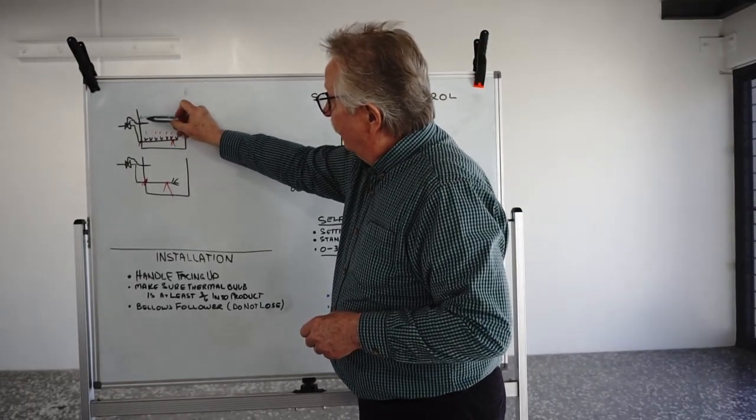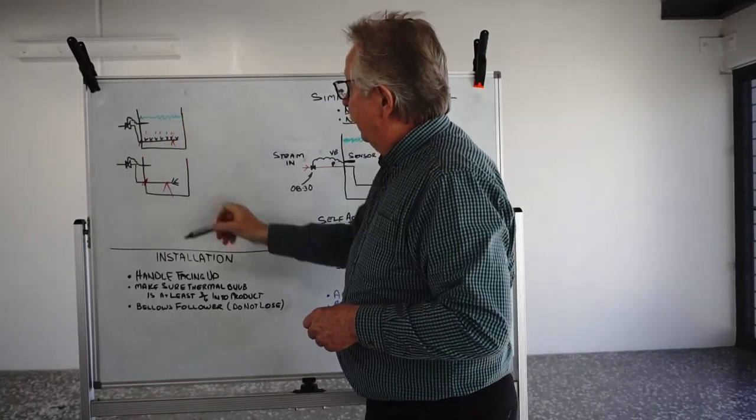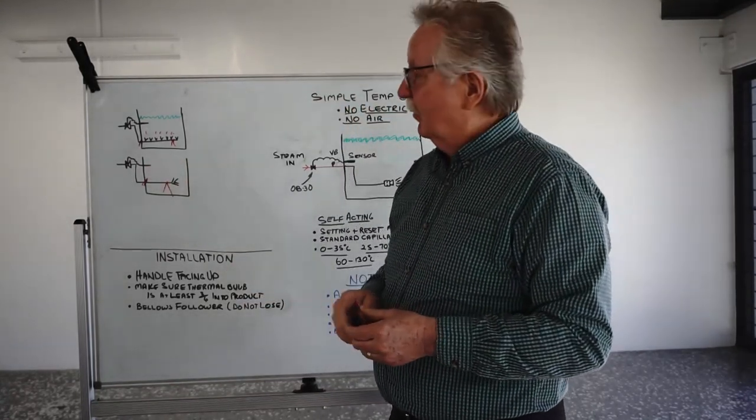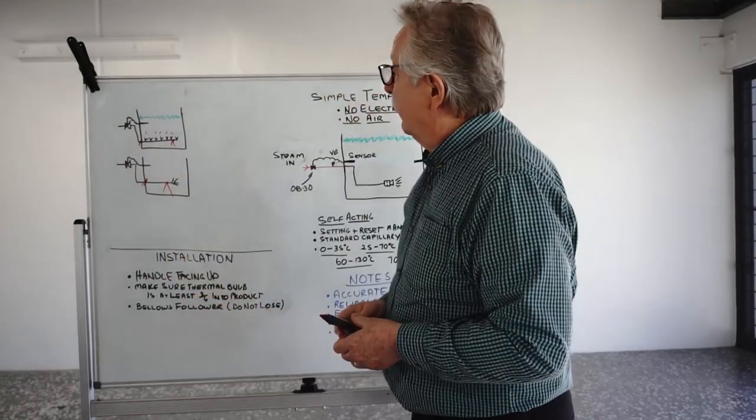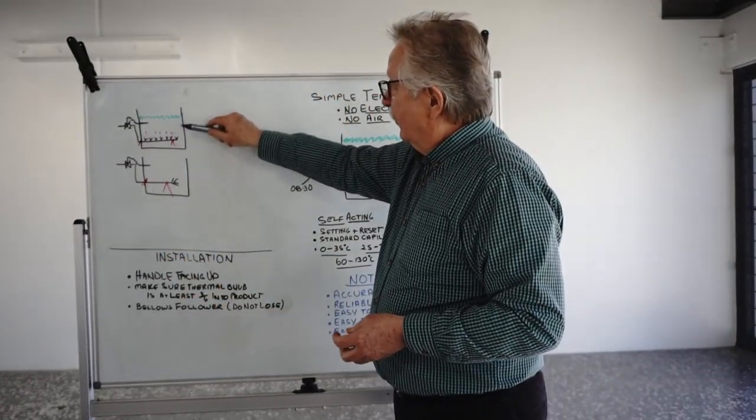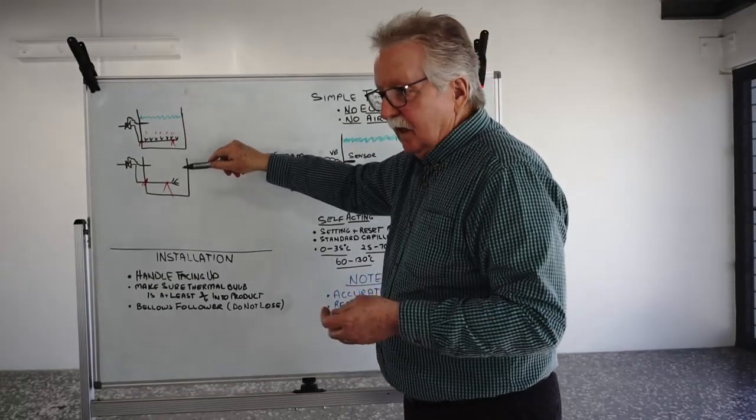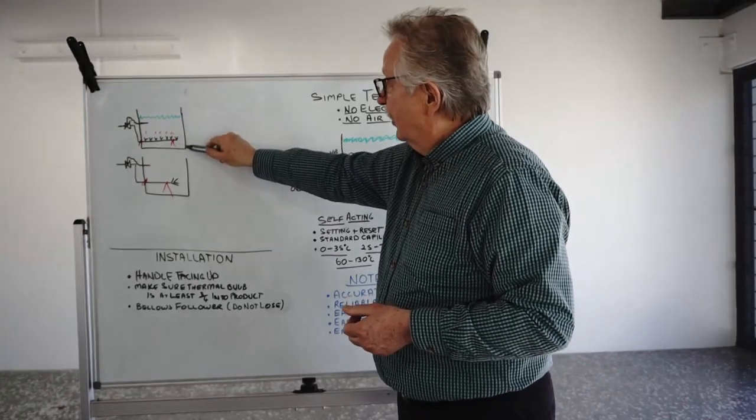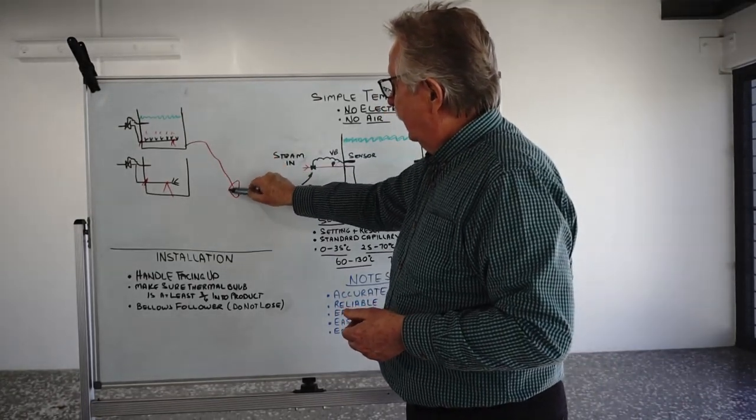A temperature control device would be on here to control the temperature in the tank. In some cases you might just see a manual valve and people turn them on and off. So in either case, it would work. You've got direct steam injection, you can heat up thousands of litres of water in this fashion and utilize it for some other process down the way.